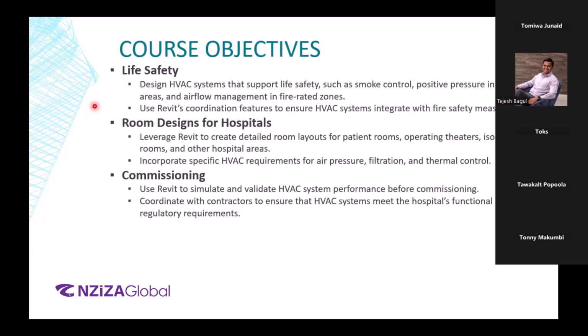That commissioning agent will go onto the field and verify whether the systems that we have designed and the contractor has built are working properly or not. If they are not, then we need to make sure that we take appropriate steps to counter any issues that might happen right away or in the future, right? But we'll still make sure that we properly understand and properly relay this information with the help of controls diagrams in Revit, so that a proper sequence of operations for different HVAC systems is established.